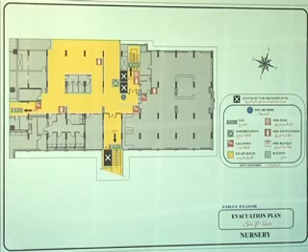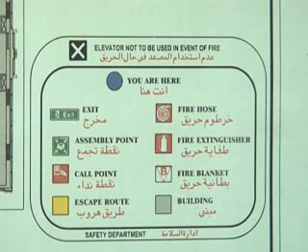First, when you are going to rescue patients, we have to feel the door handle, to be sure that there's no fire inside, it's not huge. Then we'll go inside the room and get our patient out, and then we'll confine that room by taking out the oxygen cylinders, and any flammable material could be there, and then we'll close the door and seal it very well with any towel, and preferably to be wet one.